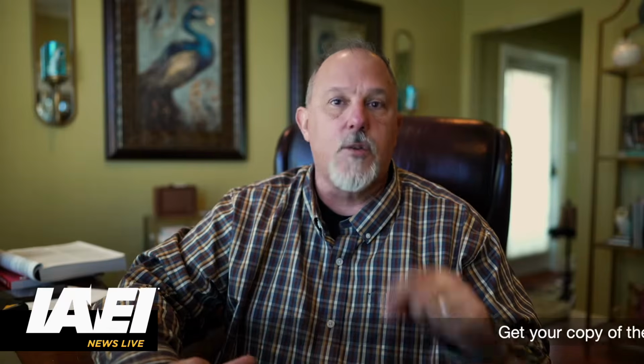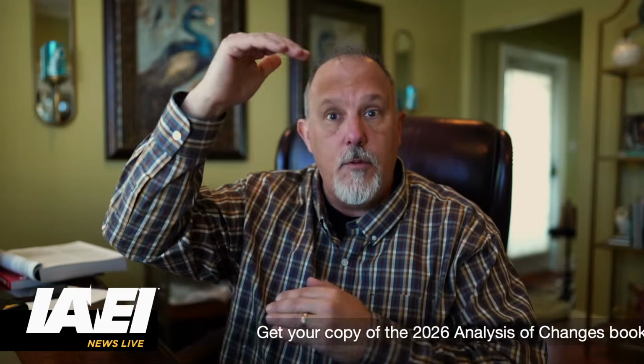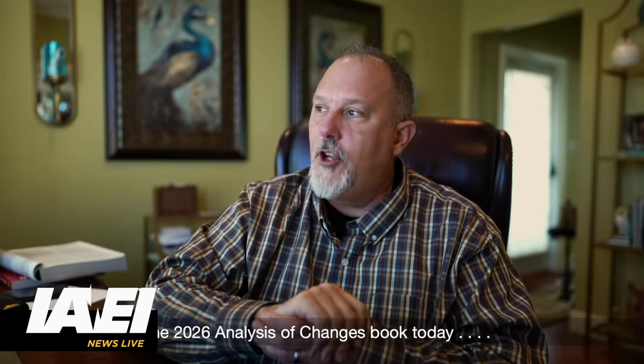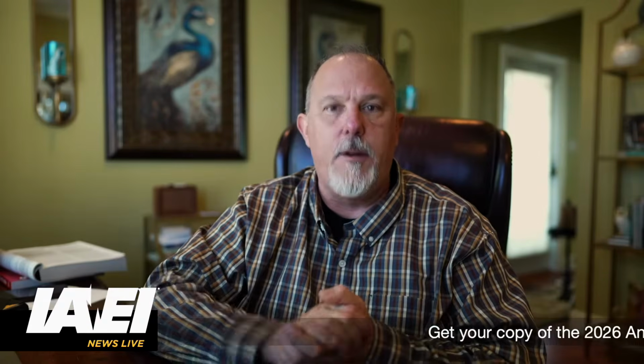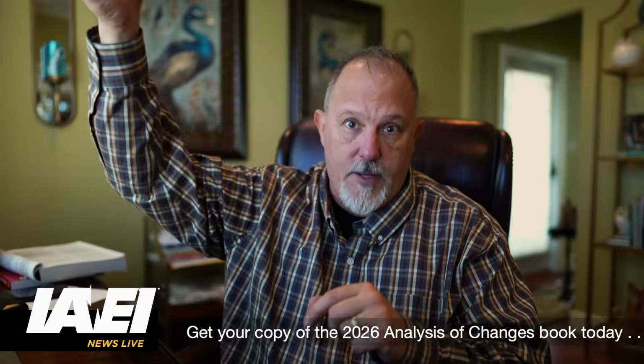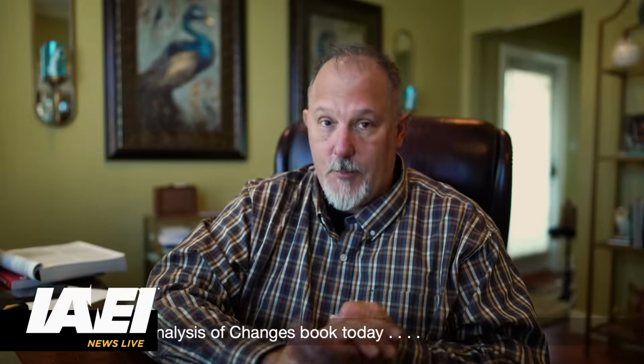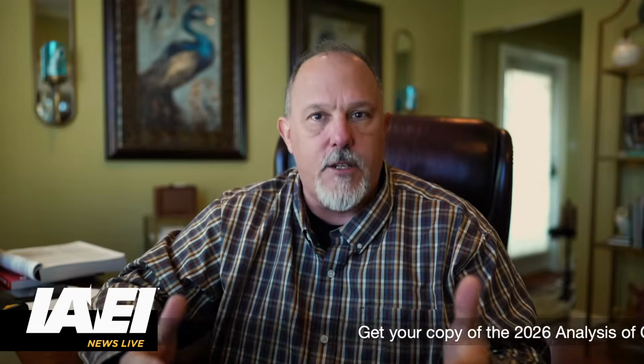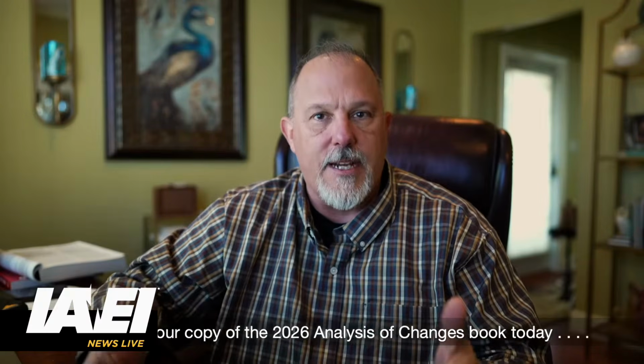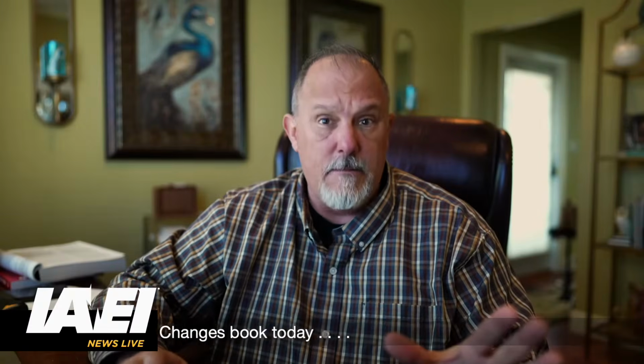I'm not going to say it's easy. I'm going to say that your sources of available fault current are minimal. You've got two, downstream and upstream. Your clearing time is pretty defined. Sort of. I mean, at the service equipment, your clearing time is dependent upon the fuse, which is upstream. For all practical purposes, you're probably going to use what we call the 2-second rule, because it's going to be such a value that it's not going to clear on an arcing fault in the secondary of that transformer. Not likely to clear. Always do your homework.